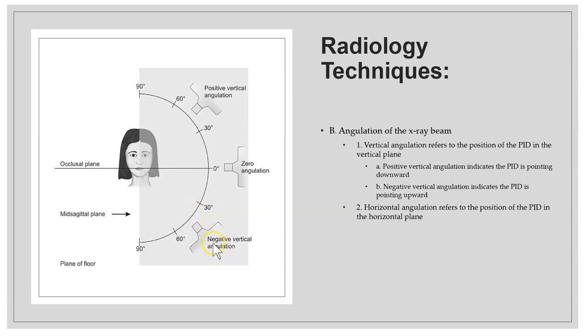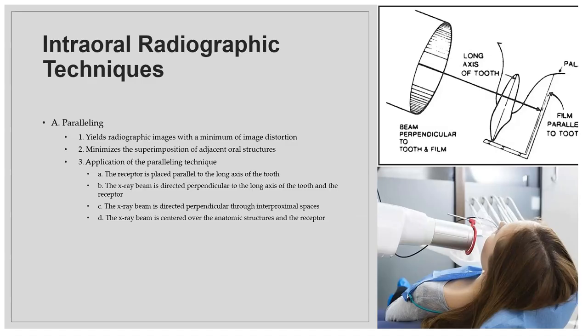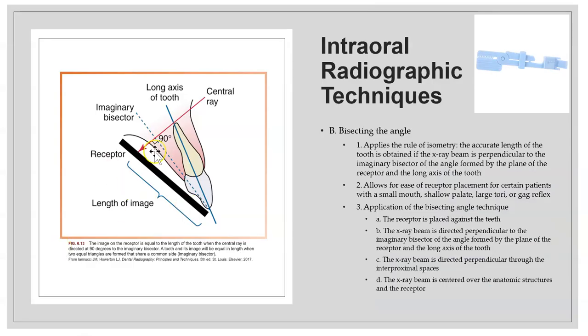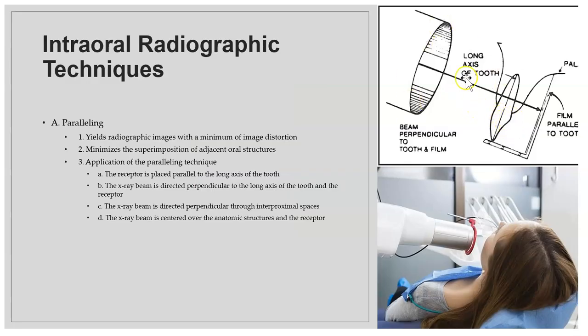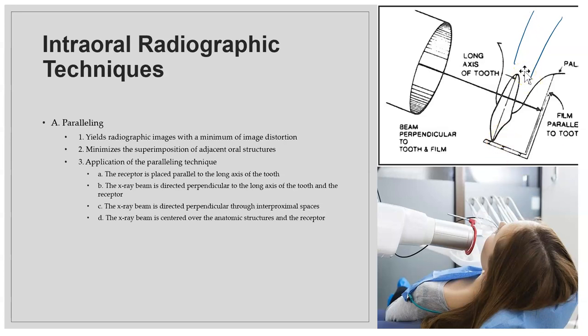Negative vertical angulation is aiming the PID from below; positive vertical angulation is aiming from above. In terms of technique, paralleling means aiming the PID directly at the tooth so the film and the long axis of the tooth are parallel to each other, with the beam perpendicular. Paralleling produces very little image distortion — no foreshortening or elongation.